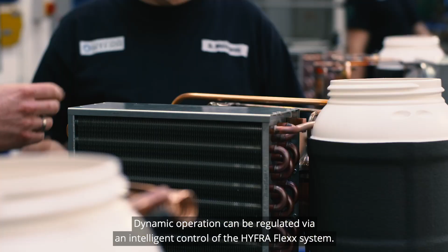Charging stations are not used evenly. At times several cars are charged at the same time, a little later none at all. Therefore, the full cooling capacity is not needed permanently. Dynamic operation can be regulated via an intelligent control of the Hyfra Flexx system, which regulates operation via the speed of the refrigeration system and reduces energy consumption to a necessary minimum.